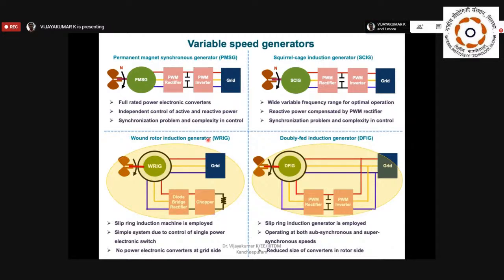So wound rotor induction generator and doubly fed induction generator. In both of these, they will use slip ring machines. This machine is also a slip ring machine, and this machine is also a slip ring machine. Depending upon the power converter topology, we name it a doubly fed induction generator. Here we say it's a wound rotor induction generator, right?